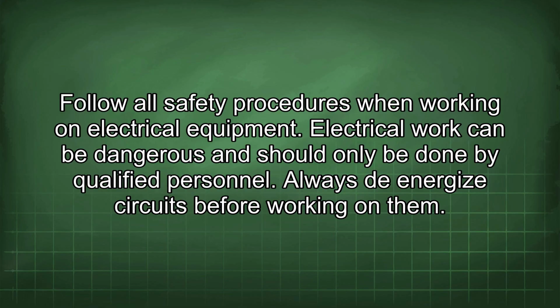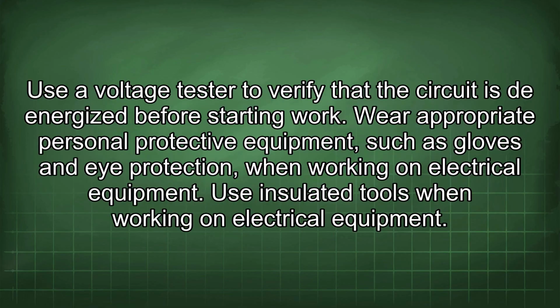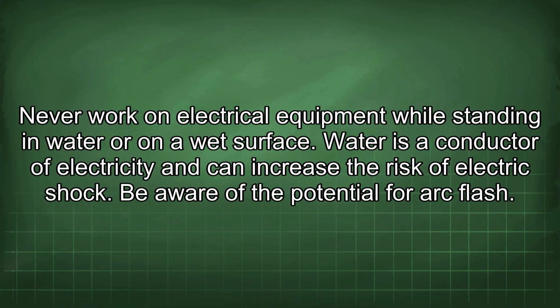Always de-energize circuits before working on them. Use a voltage tester to verify that the circuit is de-energized before starting work. Wear appropriate personal protective equipment, such as gloves and eye protection, when working on electrical equipment. Use insulated tools when working on electrical equipment. Never work on electrical equipment while standing in water or on a wet surface.